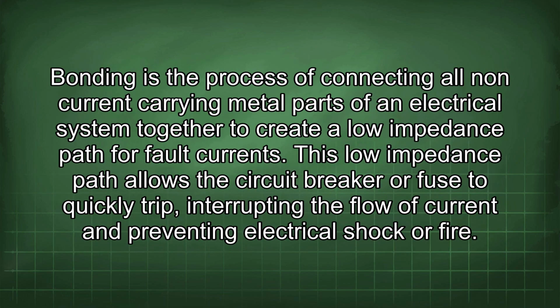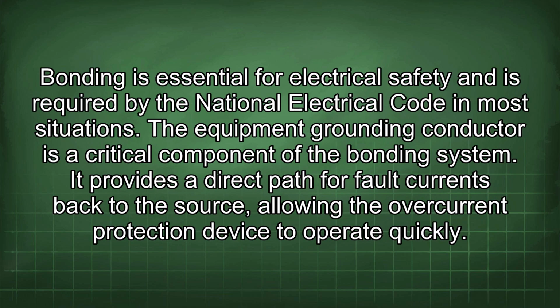Bonding is the process of connecting all non-current carrying metal parts of an electrical system together to create a low impedance path for fault currents. This low impedance path allows the circuit breaker or fuse to quickly trip, interrupting the flow of current and preventing electrical shock or fire. Bonding is essential for electrical safety and is required by the National Electrical Code in most situations. The equipment grounding conductor is a critical component of the bonding system.